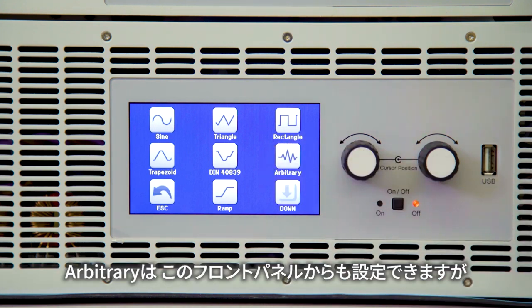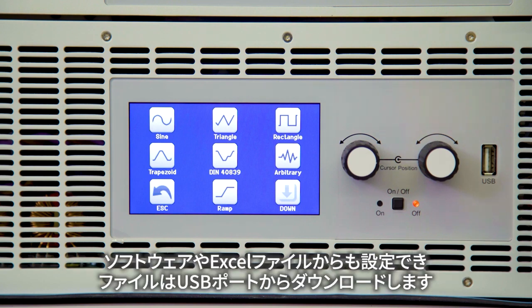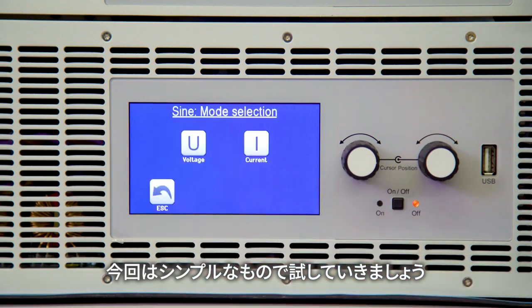The arbitrary function you can either build through the front panel, or you can go through CSV software and simply generate an Excel file and come back into it and download it directly into the source. But let's take a look at a real simple one.